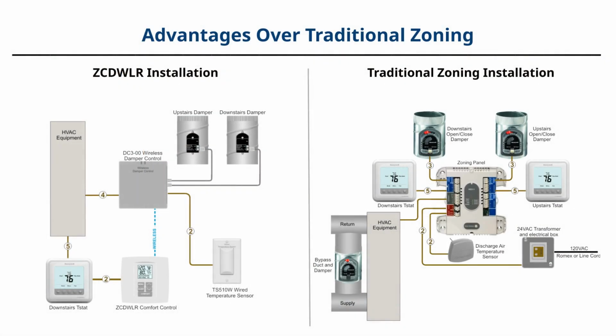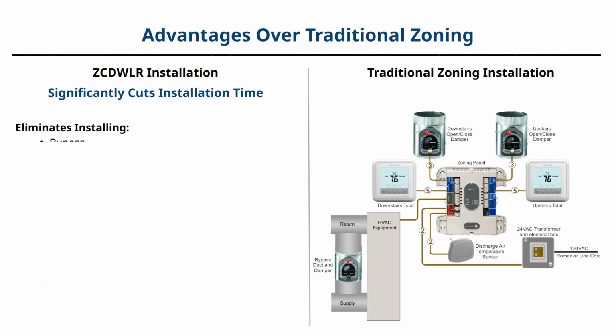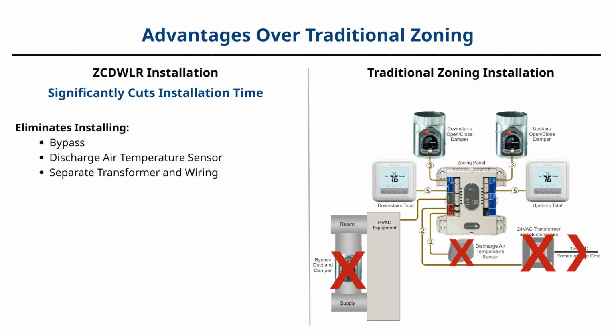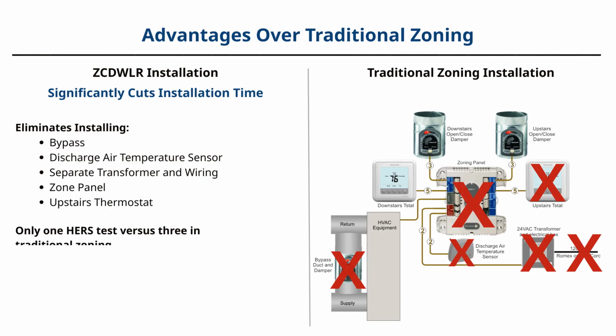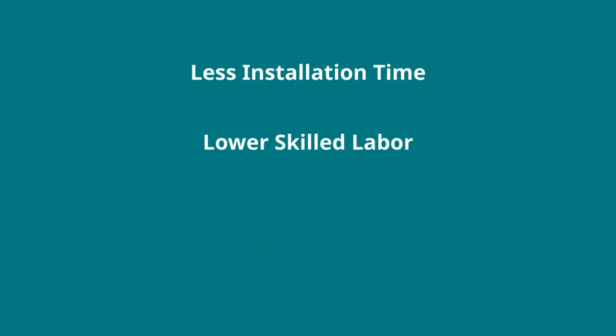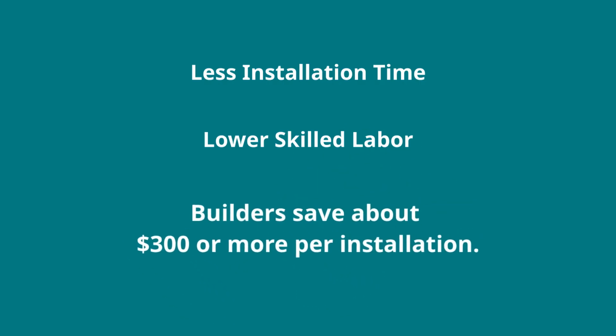The ZCDWLR features patented airflow control technology that significantly cuts installation time by eliminating installing bypass, a discharge air temperature sensor, a separate transformer and wiring, a zone panel, and an upstairs thermostat. Only one HERS test is required compared to the 3 zonal tests required in traditional zoning. Less installation time using lower skilled labor is a huge benefit when faced with a shortage of qualified labor and higher labor costs. Builders save about $300 or more per installation.